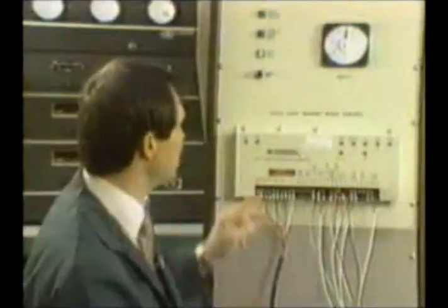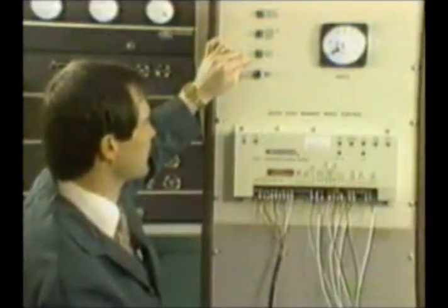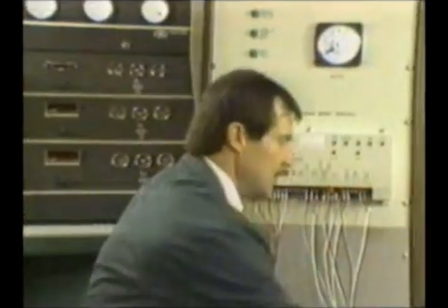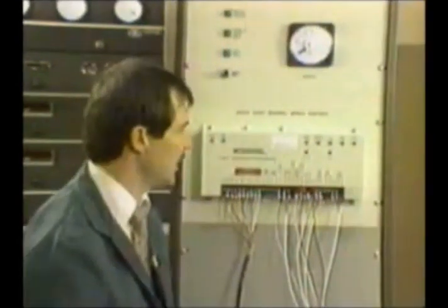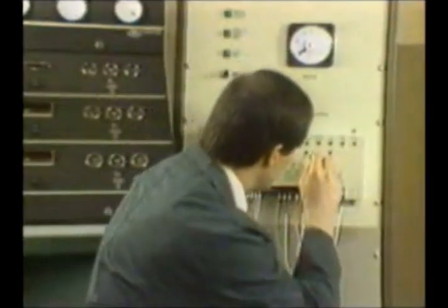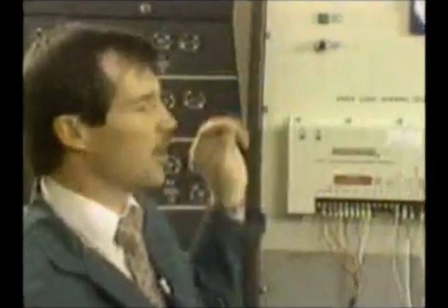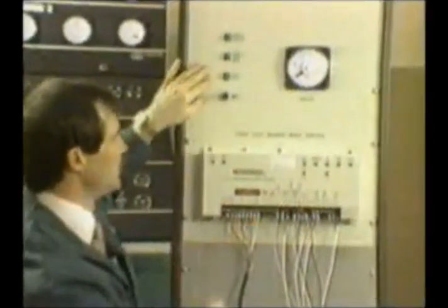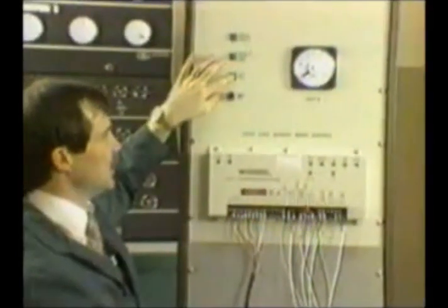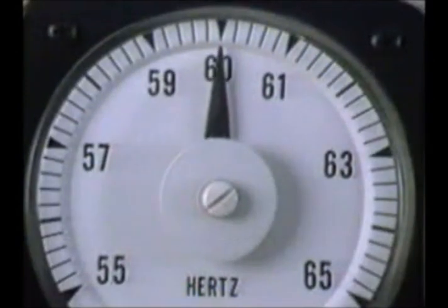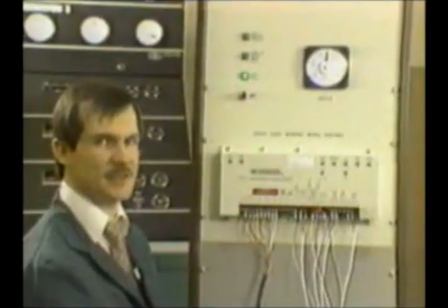Now I showed you a maximum ramp time. The maximum ramp time is 10 seconds. So let me go ahead and go back down to idle speed. And now I'm going to turn my ramp time potentiometer fully counterclockwise. Okay, now this time when I hit my close for rated switch, we're going to go up to rated speed instantly. So if you watch the Hertz meter, when I close my switch, we'll come into 60 Hertz immediately. Very smooth but very fast acceleration.